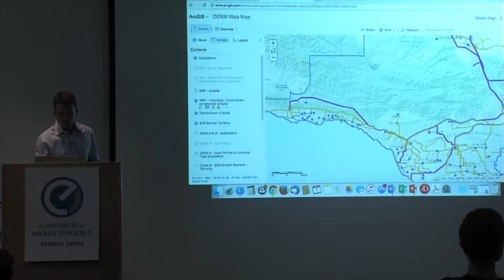The power lines are robust. They're not necessarily susceptible — if a fire passes underneath them, we can still be up, which is what happened during the Thomas fire. We had interruptions, but the reason we didn't switch over completely to the 66 was because one of those 3 lines was down for maintenance, so we couldn't do that. We had to ride it out on the 220, and that's why we saw those momentary interruptions, those blips — really problematic periodic interruptions where we're bouncing on and off, which are not good for our systems at all. So that's a little bit of context.